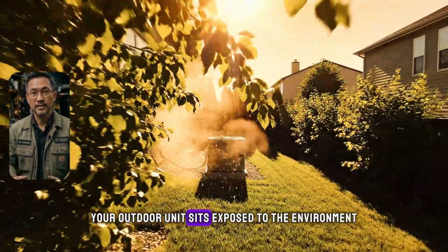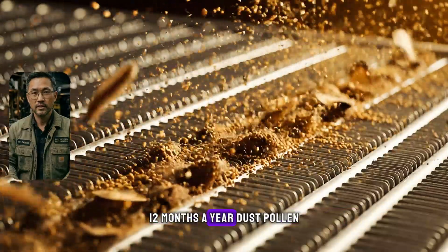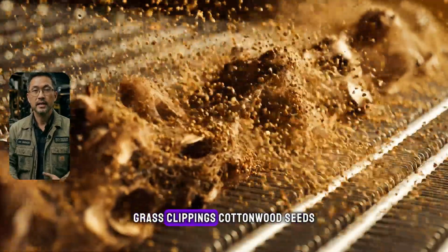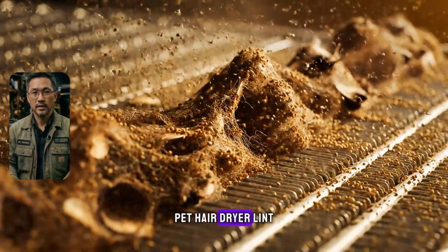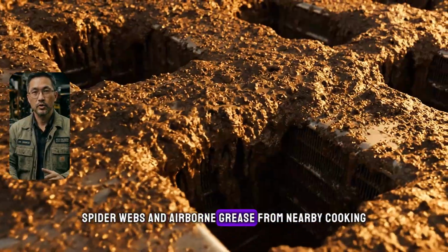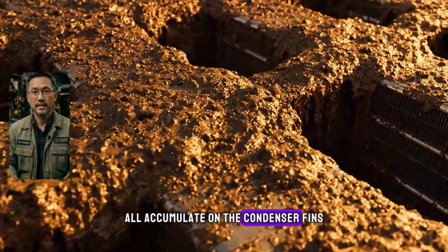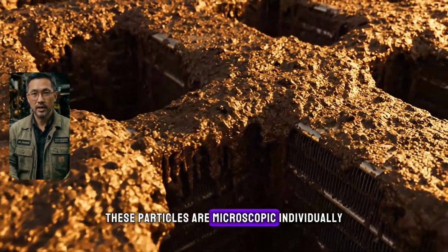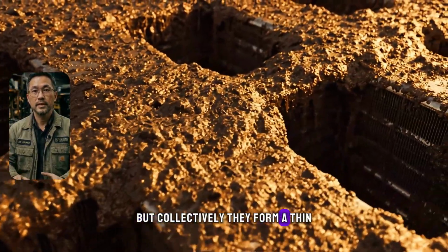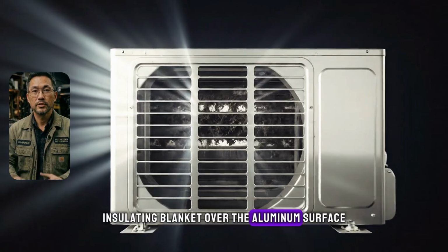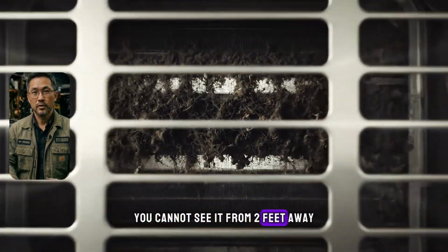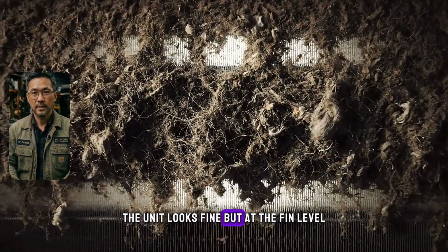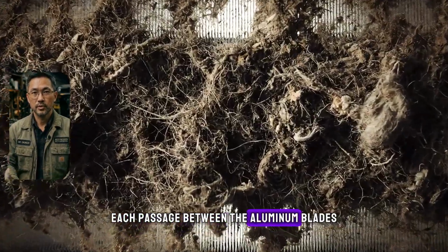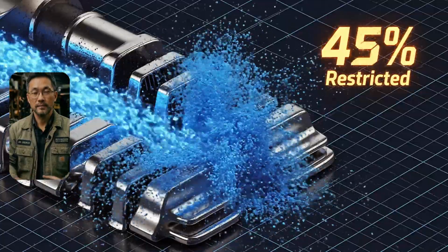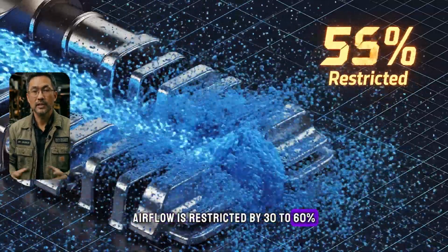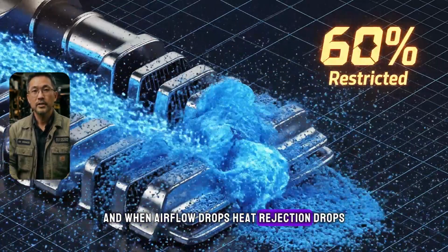Your outdoor unit sits exposed to the environment 12 months a year. Dust, pollen, grass clippings, cottonwood seeds, pet hair, dryer lint, spider webs, and airborne grease from nearby cooking all accumulate on the condenser fins. These particles are microscopic individually, but collectively they form a thin, insulating blanket over the aluminum surface. You cannot see it from 2 feet away. The unit looks fine, but at the fin level, each passage between the aluminum blades is partially or fully blocked. Airflow is restricted by 30 to 60%, and when airflow drops, heat rejection drops.